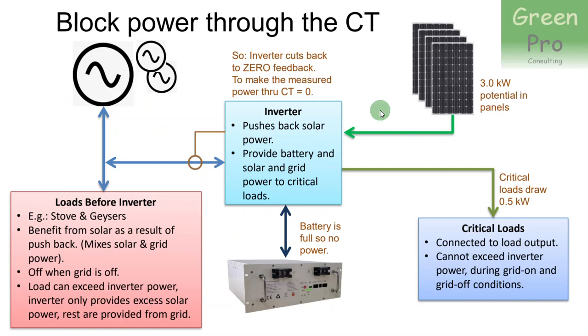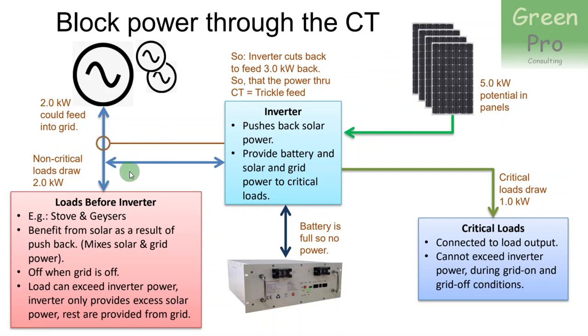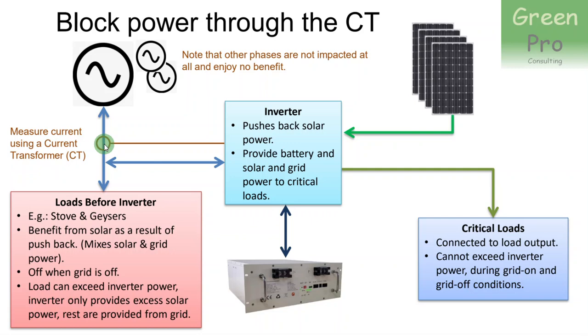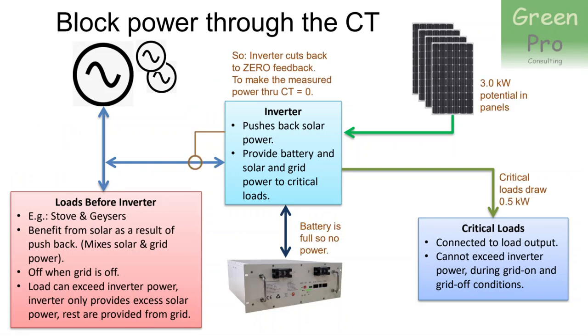The inverter cuts back to make the measured power through the CT equal to zero, meaning it's not feeding any loads before the inverter. This is the opposite of the intended use, where the inverter pushes power back to the devices before the inverter and controls the current going into the grid to zero. I hope this gives you some idea of how the CT interacts with the SunSync software and why you do not put the CT at the inverter. You have to put it where the power comes into the house, because that's the current it's going to be controlling. If you put the CT at the inverter output, it will control that to zero — and that is not what you want.